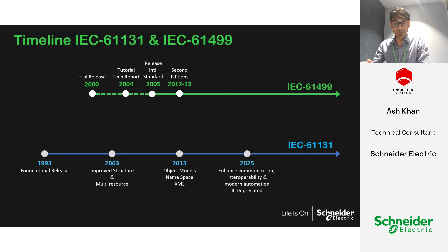So what are some of the challenges for 61131? It's cycle driven, so it scans the inputs, runs the logic, and turns the outputs on and off. It's hardware locked, so typically if you're buying a certain vendor's hardware, you also have to purchase the software that goes along with it. The software we use today typically can't be used across vendors, and even moving from one hardware to another requires a lot of re-engineering and revalidation of your code.